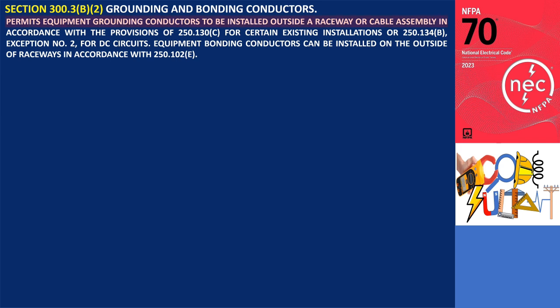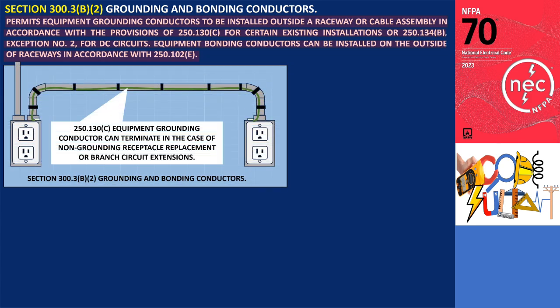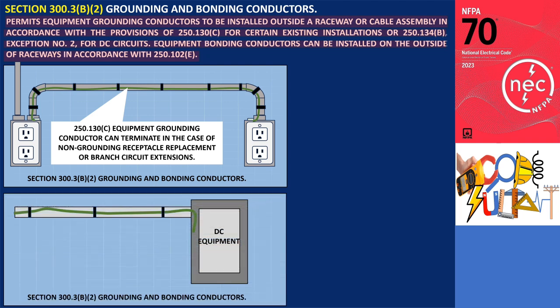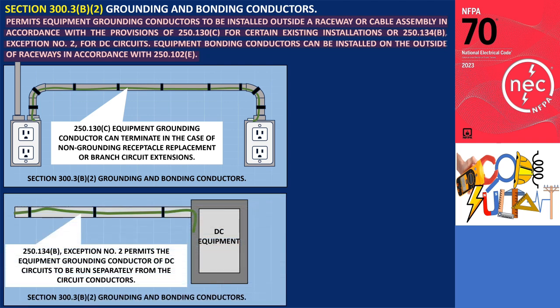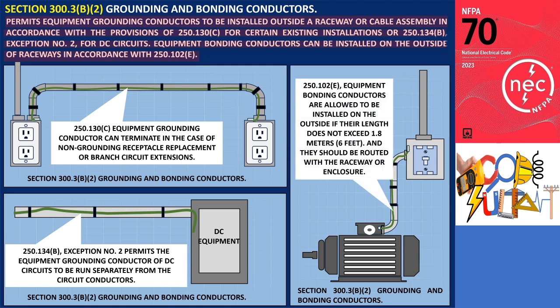Section 300.3b.2 permits equipment grounding conductors to be installed outside a raceway or cable assembly in accordance with the provisions of 250.130.c for certain existing installations, or 250.134.b Exception No. 2 for DC circuits. Equipment bonding conductors can be installed on the outside of raceways in accordance with 250.102.e. Section 250.130.c specifies where an equipment grounding conductor can terminate in the case of non-grounding receptacle replacement or branch circuit extensions. Section 250.134.b Exception No. 2 permits the equipment grounding conductor of DC circuits to be run separately from the circuit conductors. Section 250.102.e states that if equipment bonding conductors are installed on the outside, their length should not exceed 1.8 meters (6 feet) and they should be routed with the raceway or enclosure.